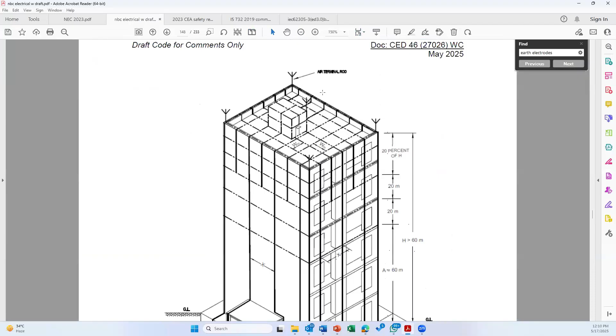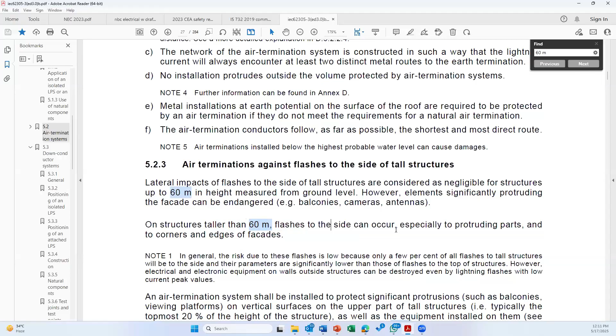I would like to draw your attention to the new and old IEC 62305. The subject is air termination against flashes to the side of tall structures. Lateral impact of flashes to the side of tall structures is considered negligible for structures up to 60 meters in height measured from ground level. However, elements significantly protruding on the facade may be endangered. On structures taller than 60 meters, flashes to the side can occur, especially to protruding parts, corners, and edges of the facade.